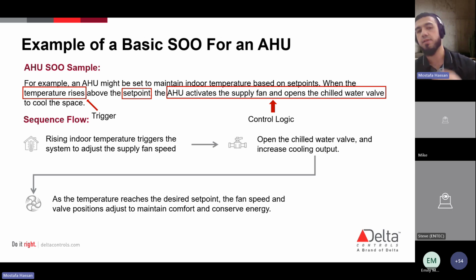And then later on, take it one step further. It doesn't just stop there. We're actually going to keep the valve open and keep using energy until the temperature reaches the desired set point. Then the fan speed and the valve positions are going to adjust to maintain comfort. Look for that bridge between comfort and conserving energy. If you no longer need the cooling output, let's close those valves. Let's ramp down the fan speed for the air handling unit.